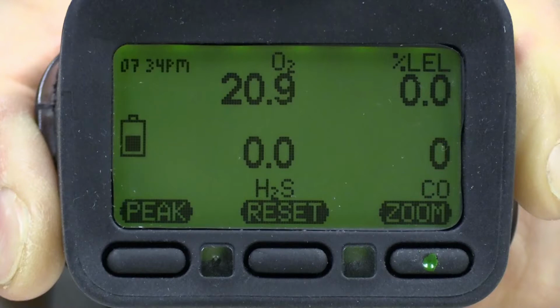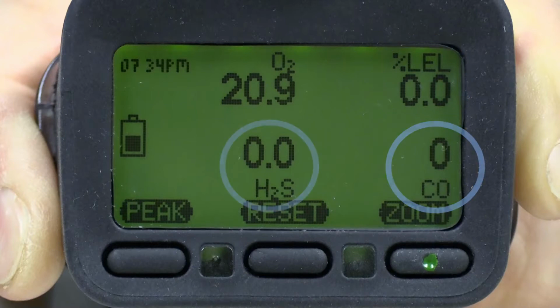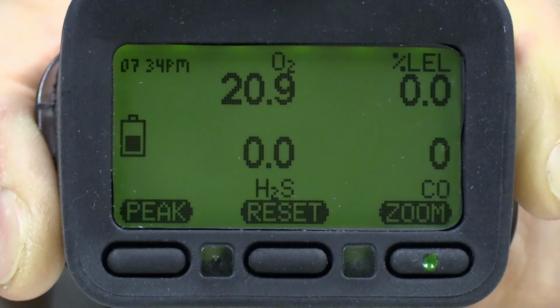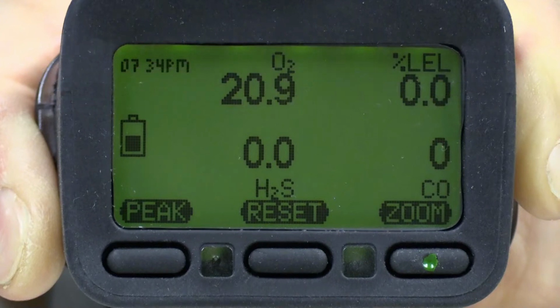The readings in fresh air should be 20.9% for oxygen, 0% LEL for combustible gas, 0 ppm for carbon monoxide, and 0 parts per million for hydrogen sulfide. Make sure to give the instrument a chance to stabilize completely before proceeding to perform a fresh air autocal or a gas autocal calibration adjustment.